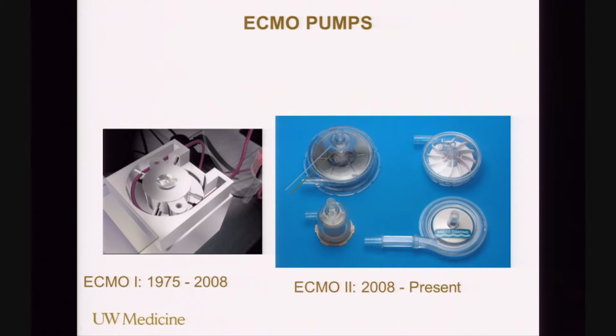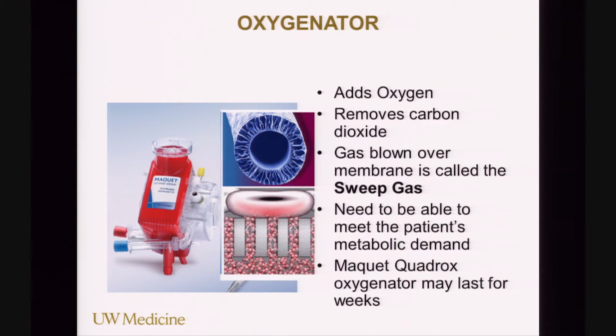The oxygenators: the unit that most people are using now is the Maquet unit, and they make an oxygenator by itself. So the oxygenator and pump combined dramatically decrease the surface area that you have to work across. The gas is basically blown over the membrane. It's usually oxygen, and that's called the sweep gas, and the rate of that sweep gas is the minute ventilation of the patient. It's how quickly oxygen and CO2 are exchanged.